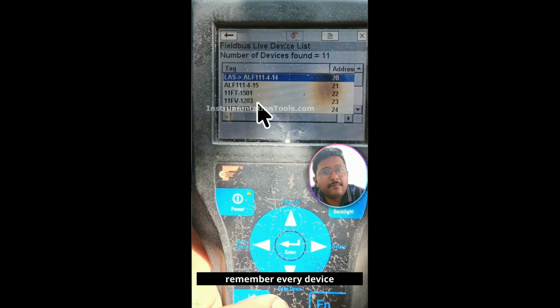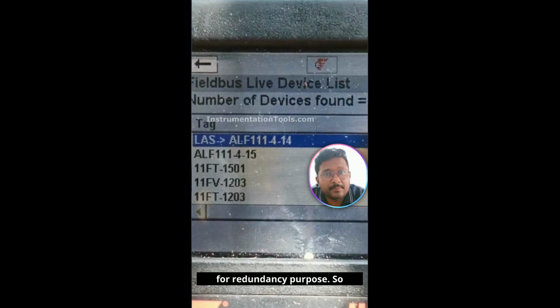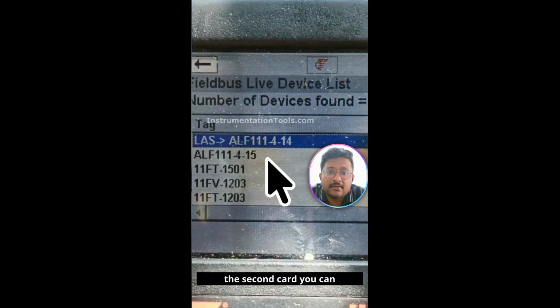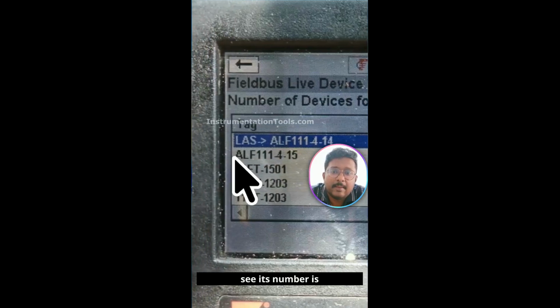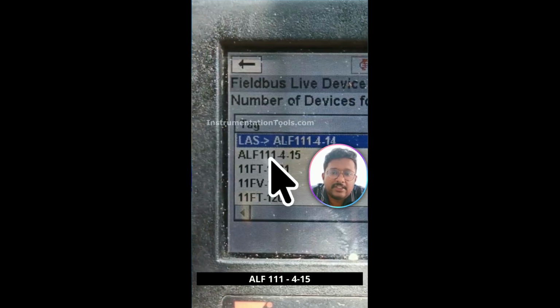And remember, every device has a device address in Foundation Fieldbus. For this LAS, the device address is 20. Similarly, we have two LAS cards. We have two Foundation Fieldbus cards in our DCS system for backup and redundancy purposes. So the second card, you can see its number is ALF 111 4 15, the next one, and its address is 21.